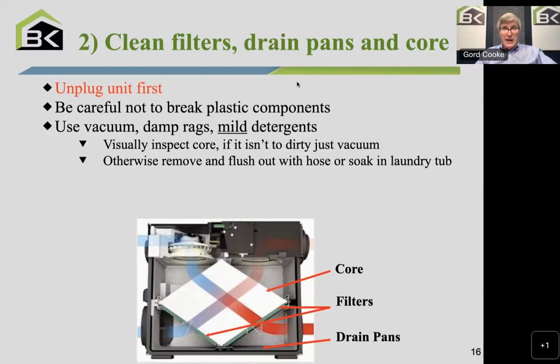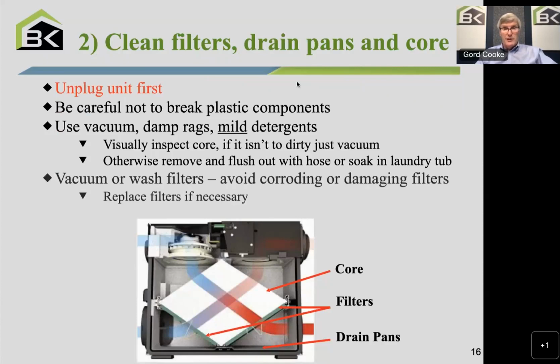And then you're going to damp wipe the drain pans where the condensate water has been dripping, just damp wiping out that device. And so as I say, you're vacuuming or washing the filters. You don't use any corrosive or strong cleaners. They don't need it. But the filters, as I say, I normally find every 5 years or so, you vacuum them 3 times a year for 5 years. They're getting pretty ragged.